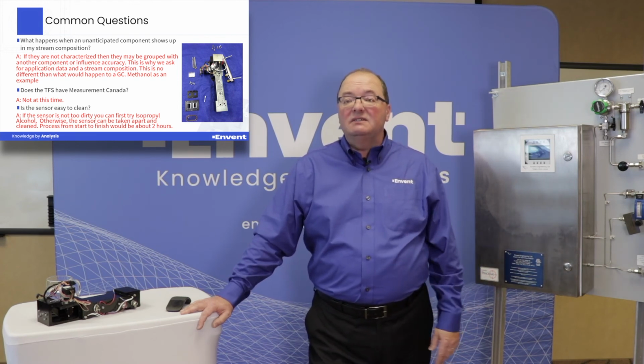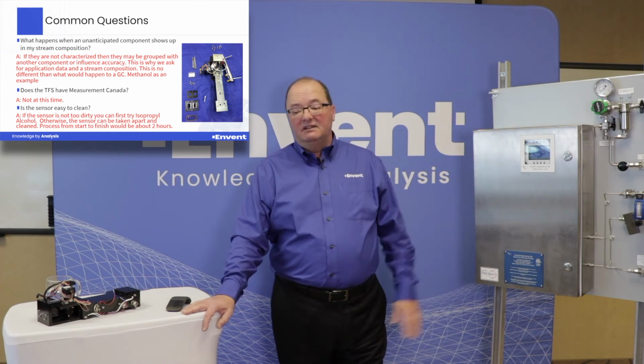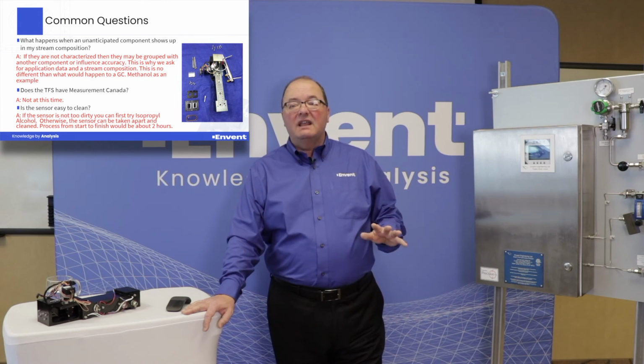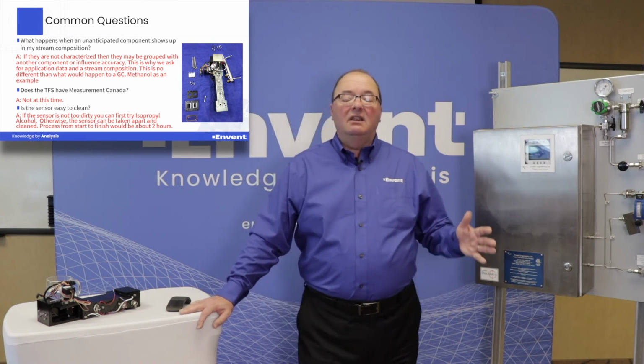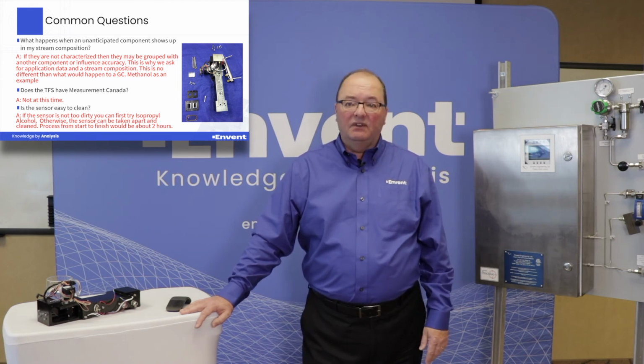Another question is, does the TFS have Measurement Canada? The answer is not at this time, and typically we would never see that. This is more of a process analyzer and not going down to the levels that you require in order to achieve that Measurement Canada certification.